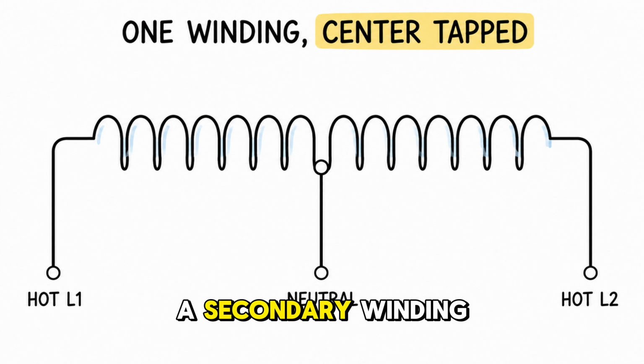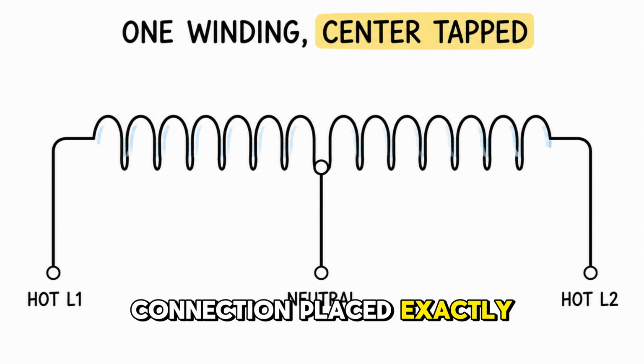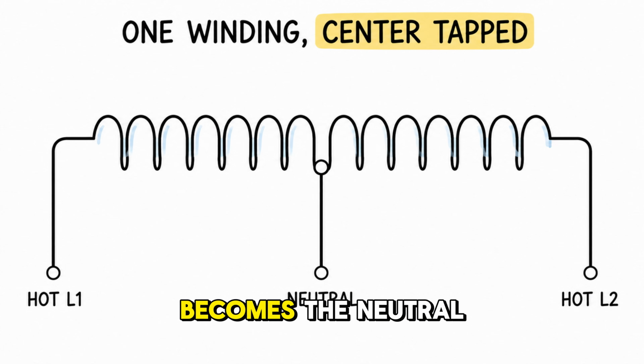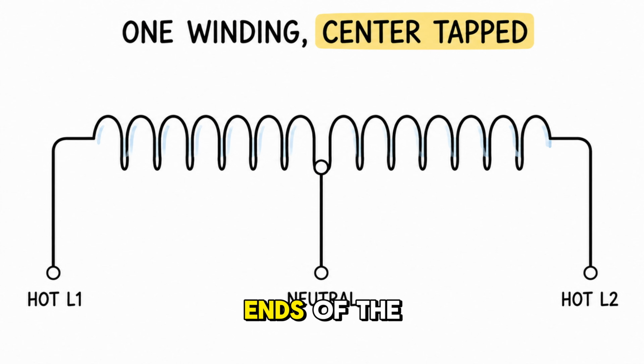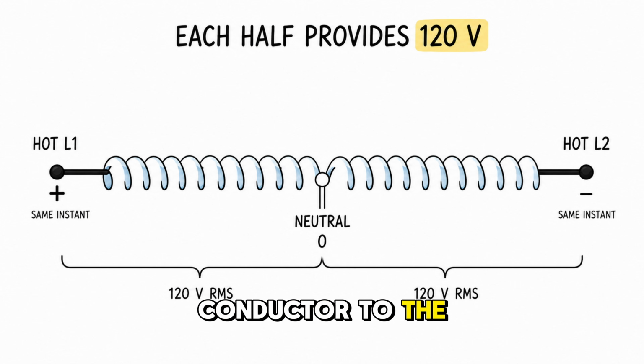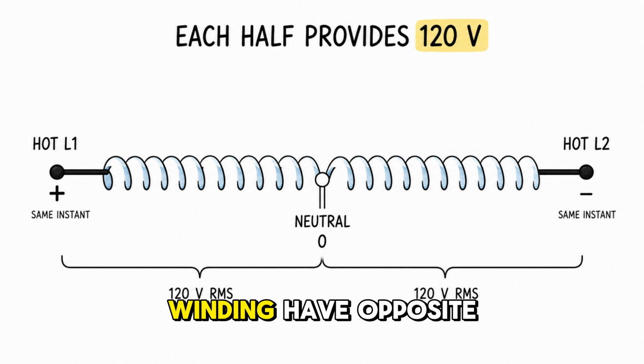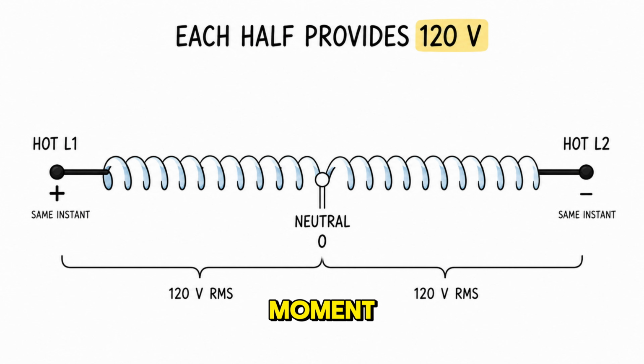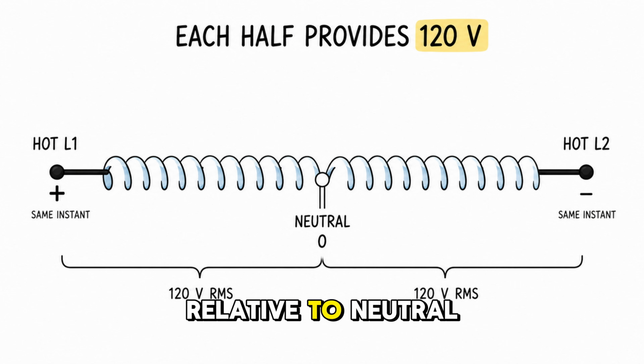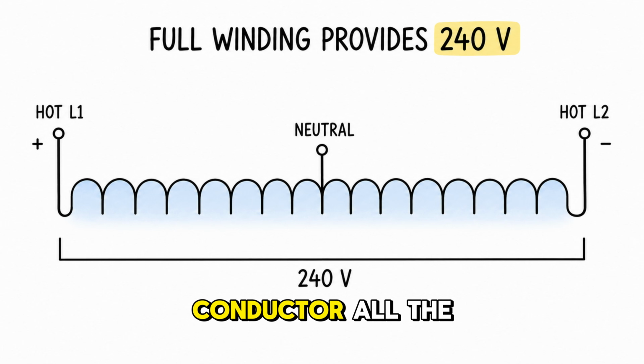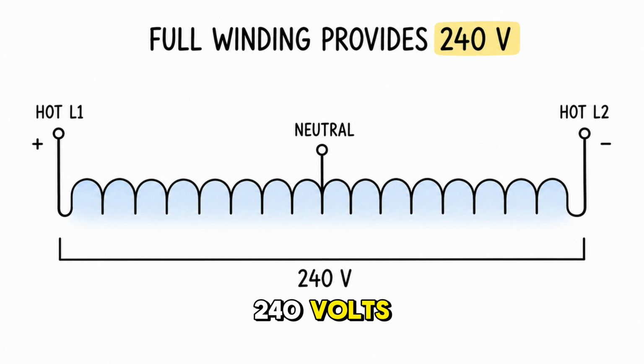Inside the transformer is a secondary winding. Picture it as one continuous coil with a connection placed exactly in the center. This center connection becomes the neutral conductor, while the 2 ends of the same winding become the 2 hot conductors. From either hot conductor to the center neutral, the voltage is 120 volts. But the 2 halves of the winding have opposite polarity at any given moment. When one end is positive relative to neutral, the other end is negative relative to neutral. Measuring from one hot conductor all the way to the other, therefore, uses the complete winding and gives 240 volts.